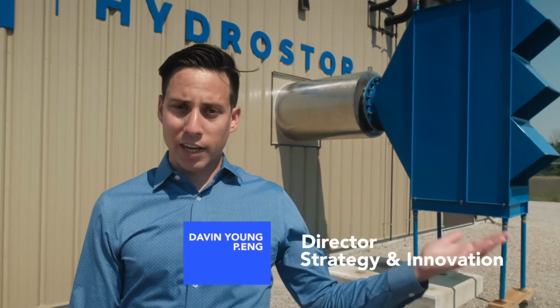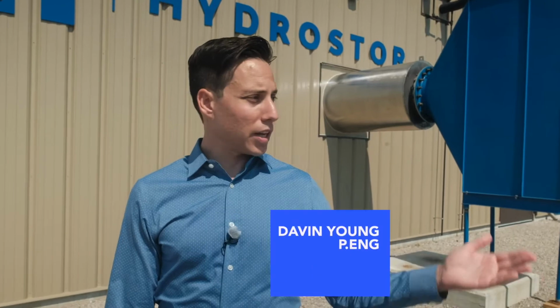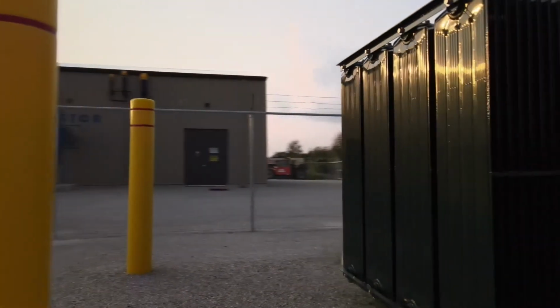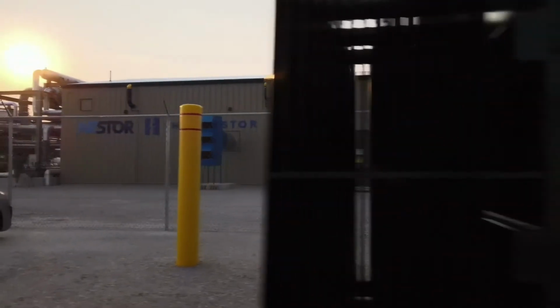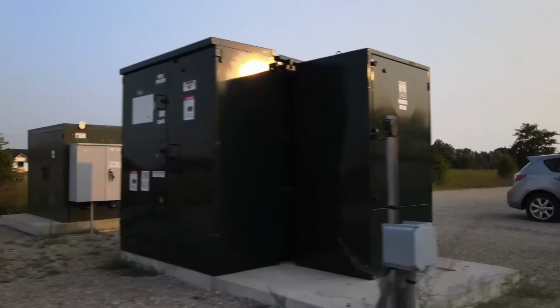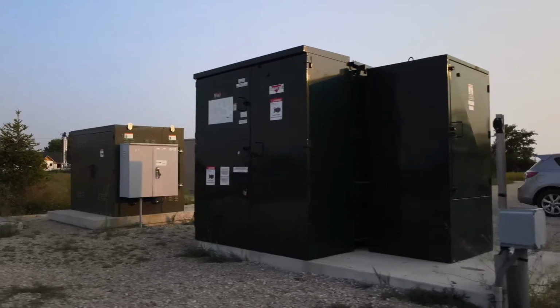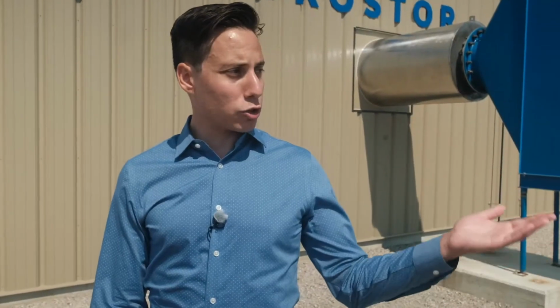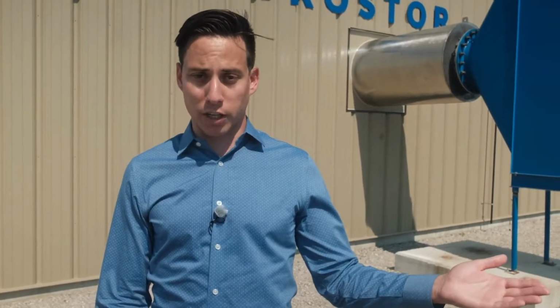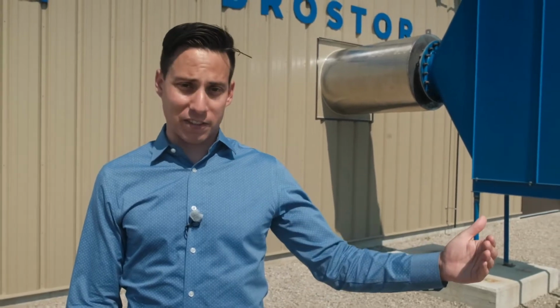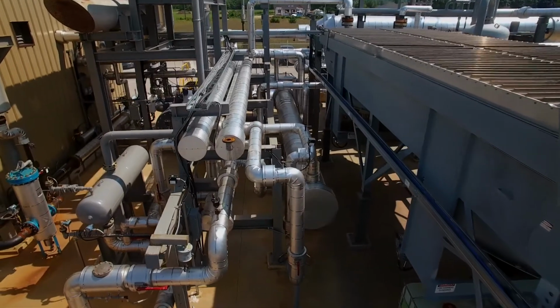The transformer is the connection point to the electricity grid. It is connected via an underground cable that goes up the road to the substation. It transforms between the distribution voltage and the voltage of electricity that's used by the compressor and turbine in the facility. Electricity is drawn from here while the A-CAES system is charging, and electricity is provided back to the facility through the transformer while the facility is discharging.